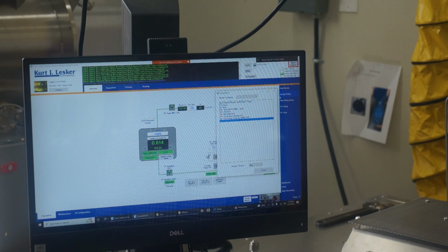So if you want to have a barrier layer on a sample that you're going to stick in an etching source, I would use that, because you can put a thick layer fast as a barrier layer for your next process. I wouldn't use the ALD tool as a barrier layer because it's slow and the chemistry is more expensive.